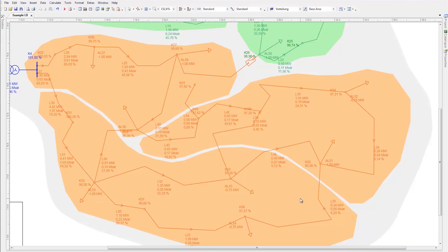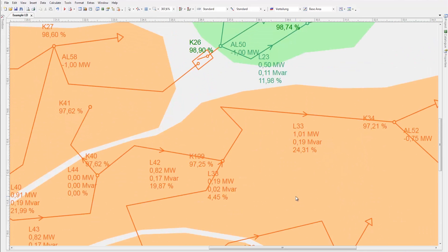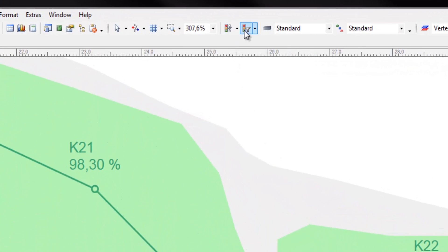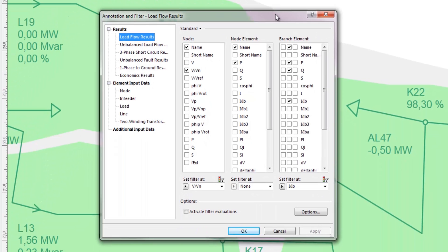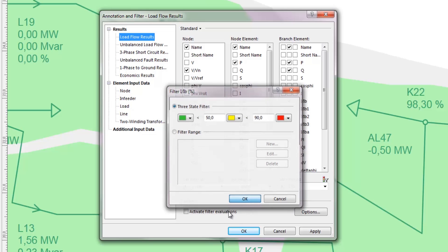PSS SINCAL provides many powerful tools for visualization of results to clearly see the network condition without reading numbers. The network results can be color coded. For example, nodes can be coded according to voltage: voltages between 97 and 103 percent can be colored green to signify acceptable values, and voltages outside this range can be colored red. Utilization of branch elements can also be coded where red signifies values over 90 percent, yellow values between 50 and 90 percent, and green values below 50 percent. Activate the filter function to see the visualization of results.